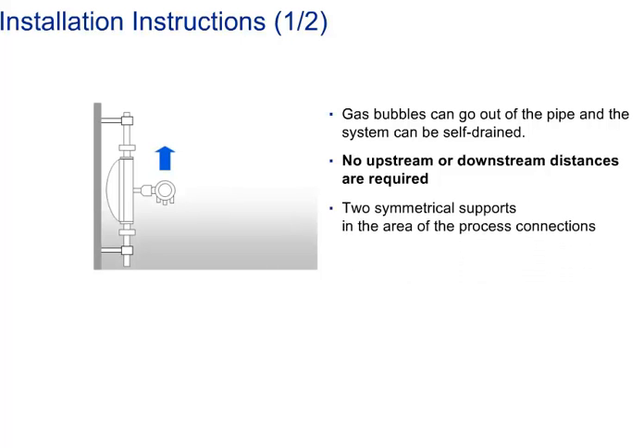Supports should be installed symmetrically either side of the flow meter and close to the process connections, but not directly on the meter housing.